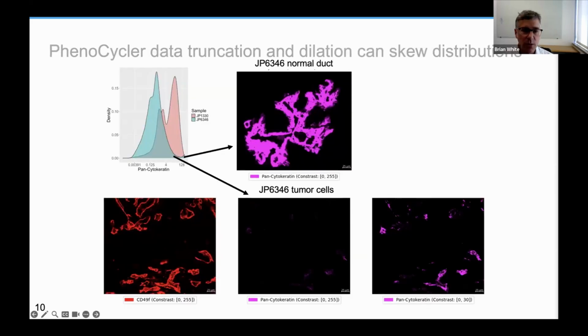Storage of these large data was also made more cost-effective because of several properties of the PhenoCycler, that is the codex instrument, and this proprietary QP-TIFF format. Most obviously, and maybe not as interestingly, the QP-TIFF uses LZW lossless compression. But beyond that, the PhenoCycler attempts to optimize the signal to noise by truncating and then dilating the native 16-bit data into the 8-bit representation in the QP-TIFF. And this does have some unfortunate analysis consequences. It's susceptible to hotspots setting the high end of the dynamic range, and that's pushing potentially meaningful biological data, not necessarily into the noise floor, but kind of dangerously close to it.